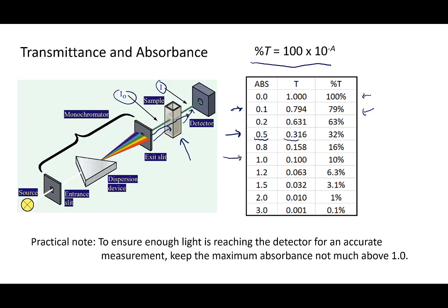An absorbance value of 1 means only 10% of light gets through — for every 100 photons in, only 10 escape to the detector. At absorbance 2, only 1% gets through; at absorbance 3, only 0.1%. Because of this, anything above about absorbance 1 has very little light hitting the detector, making the detector response inaccurate. To keep measurements accurate, you generally don't want to go much above 1. If you see a spectrum with a maximum of 2.5 or so, those values are just not credible.